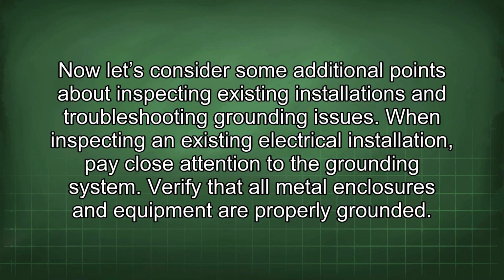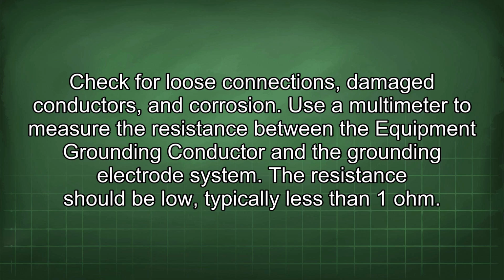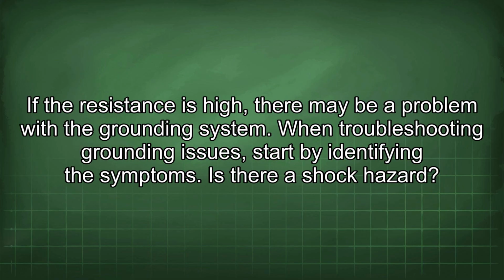When inspecting an existing electrical installation, pay close attention to the grounding system. Verify that all metal enclosures and equipment are properly grounded. Check for loose connections, damaged conductors, and corrosion. Use a multimeter to measure the resistance between the equipment grounding conductor and the grounding electrode system. The resistance should be low, typically less than 1 ohm. If the resistance is high, there may be a problem with the grounding system.